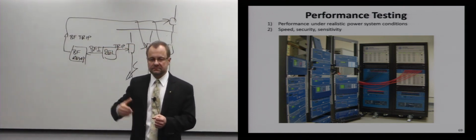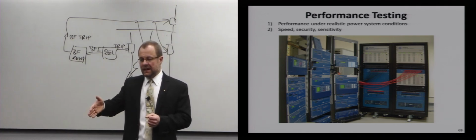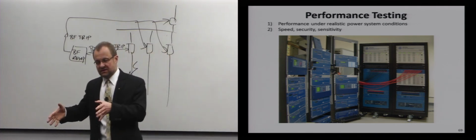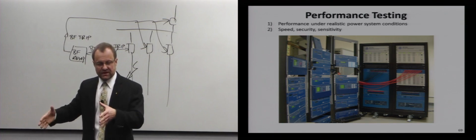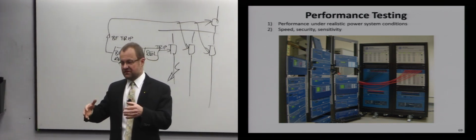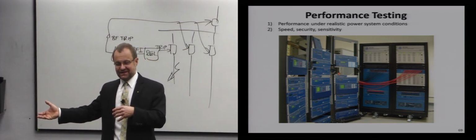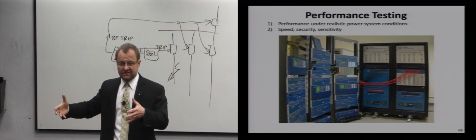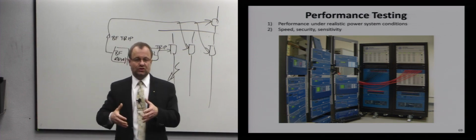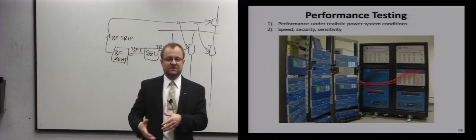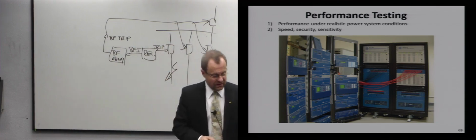So this way, you could simulate a lot of relays, a lot of faults, and you have a closed-loop situation. When you place a fault, some relays should detect it. They will open the circuit breakers, and on top of that, you could have 50 other relays that see all of that, and you watch them to see that they don't operate, because they shouldn't, right? So that's the beauty of closed-loop testing.